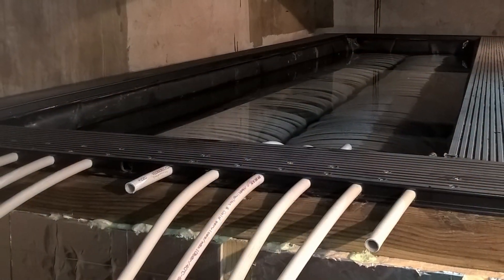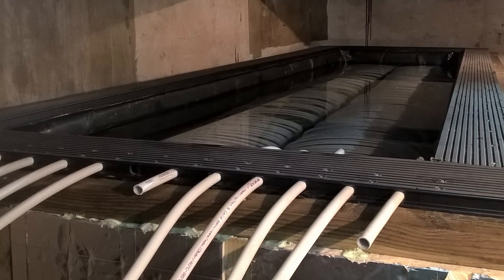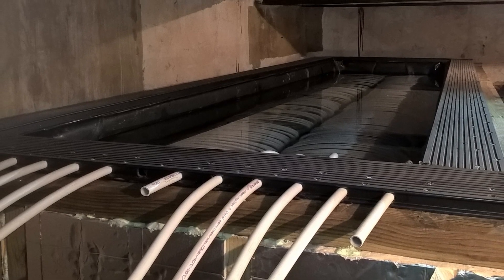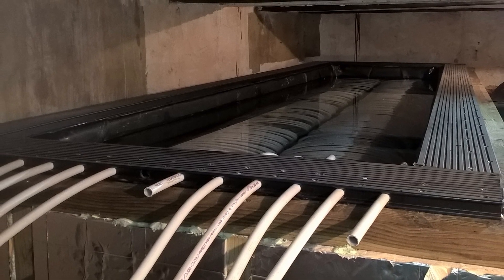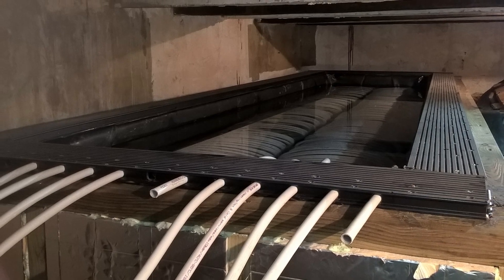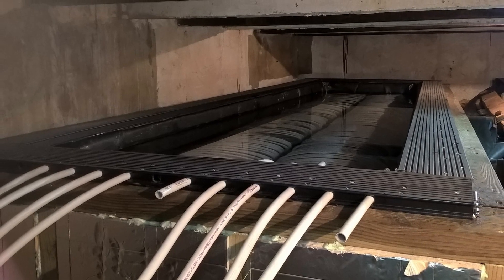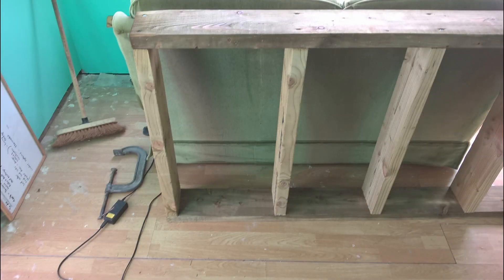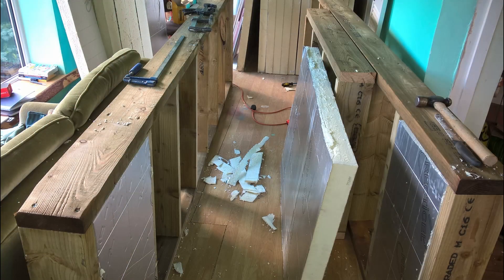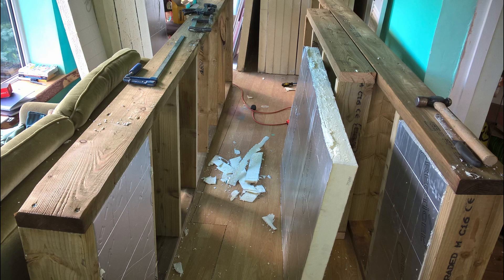Here's the storage tank with its lid off. The tank is a freestanding tank made with a 6x2 frame which is fully filled with polyurethane insulation, and then there's another 50mm on the inside of the tank, bringing the total insulation to 200mm all round. The inside of the tank is lined with OSB board and has an EPDM waterproof membrane over the whole thing.